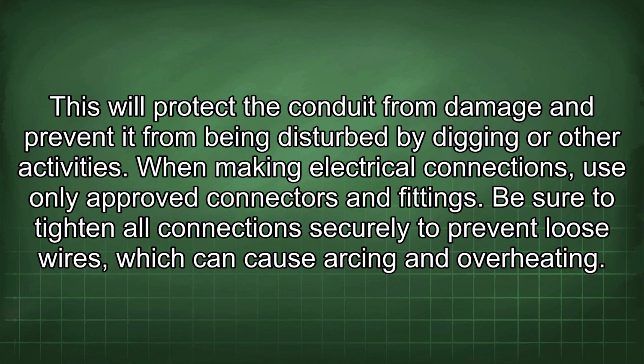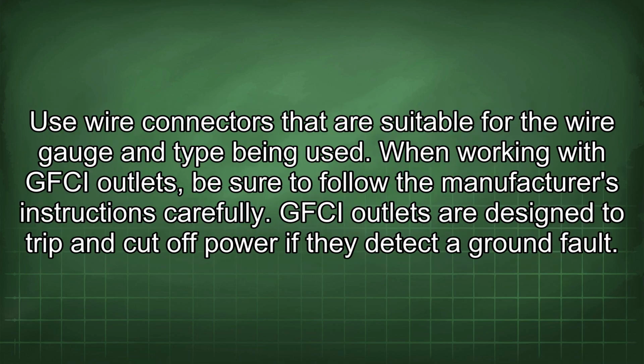When making electrical connections, use only approved connectors and fittings. Be sure to tighten all connections securely to prevent loose wires, which can cause arcing and overheating. Use wire connectors that are suitable for the wire gauge and type being used.